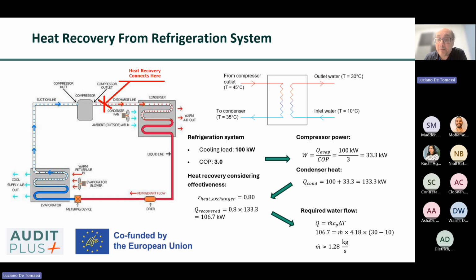profile and system design. The amount of heat that can be recovered is closely linked to the refrigeration system's coefficient of performance. The COP defines the ratio of useful cooling output to electrical input, and by energy balance, the rejected heat is the sum of both. For example, if a system has a COP of 3, it produces 3 units of cooling for every 1 unit of electrical energy consumed, meaning that approximately 4 units of heat are rejected at the condenser: 1 unit input plus 3 units extracted from the cooled space.